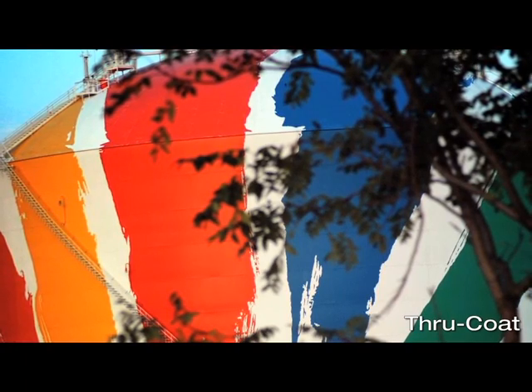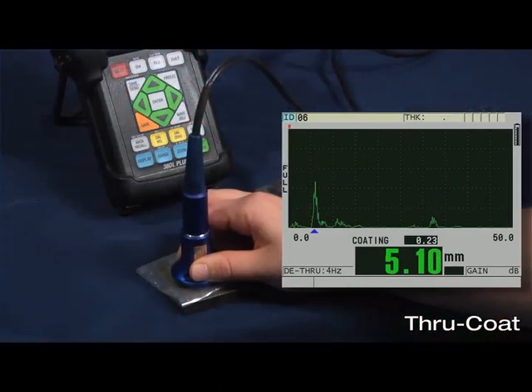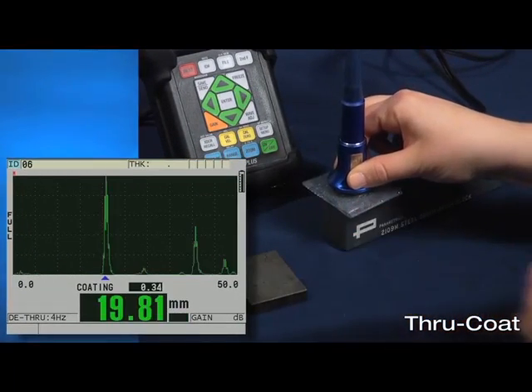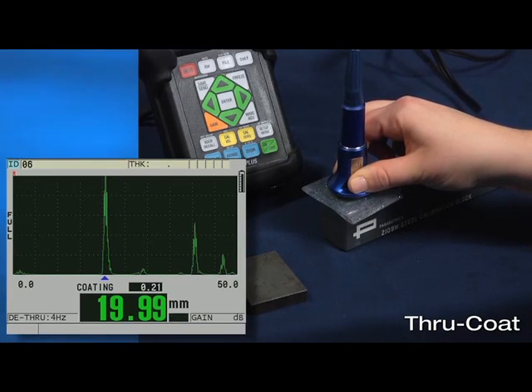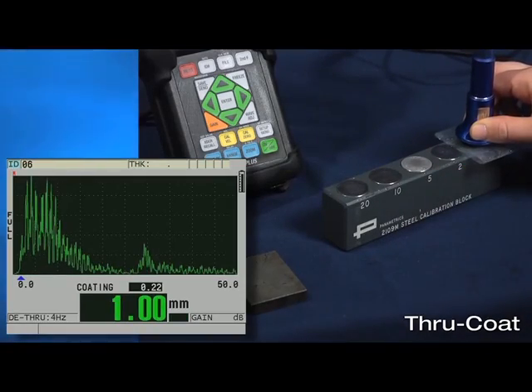The advantages of Thru-Coat are that it can make proper thickness measurements when multiple back wall echoes do not exist, or when measuring thick and thin materials, as demonstrated here. Here is a Thru-Coat measurement when multiple back wall echoes do not exist. Here is a Thru-Coat measurement on a 20 mm test block. Here is a Thru-Coat measurement on a 1 mm test block.